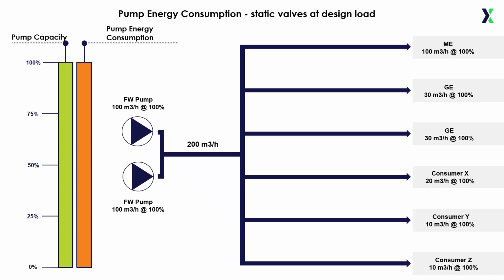This slide illustrates the relationship between pump capacity and energy consumption in a vessel's cooling water system. The system is balanced by static valves. At full design load, the freshwater pumps each operate at 100 cubic meters per hour, alongside the main engine at 100 cubic meters, two gensets at 30 cubic meters each, and additional consumers with smaller demands, 20, 10, and 10 cubic meters respectively. Altogether, this results in a total pump capacity requirement of 200 cubic meters per hour at 100% load. At design load, the pump energy consumption is also 100%.